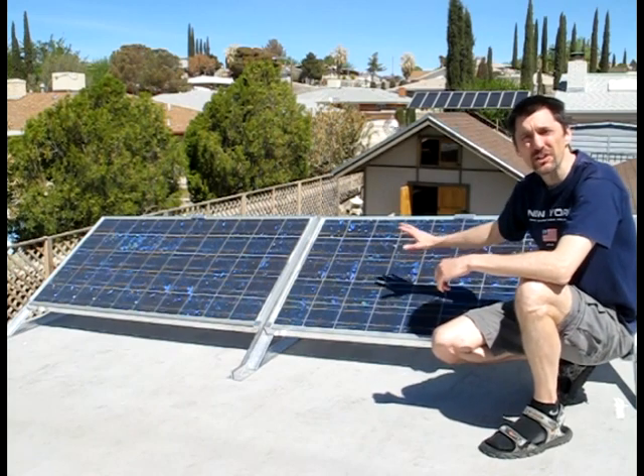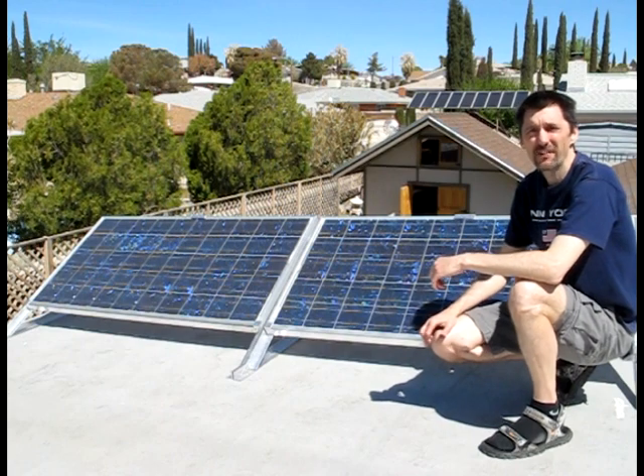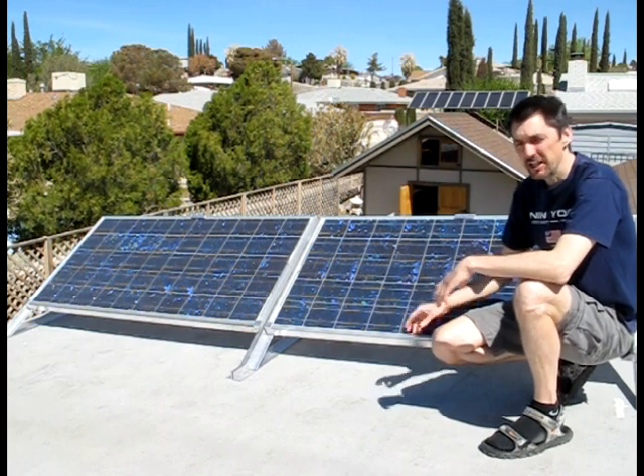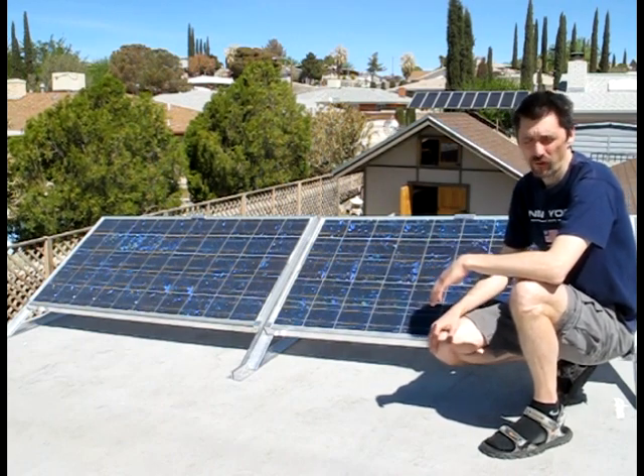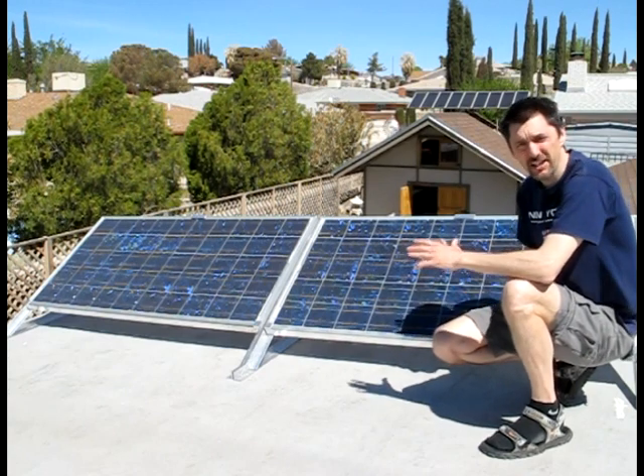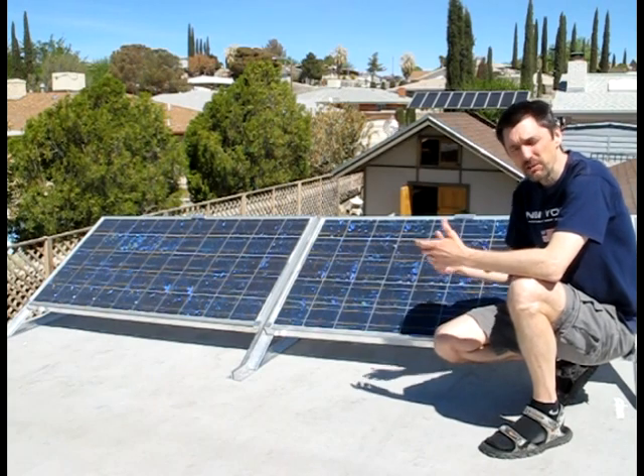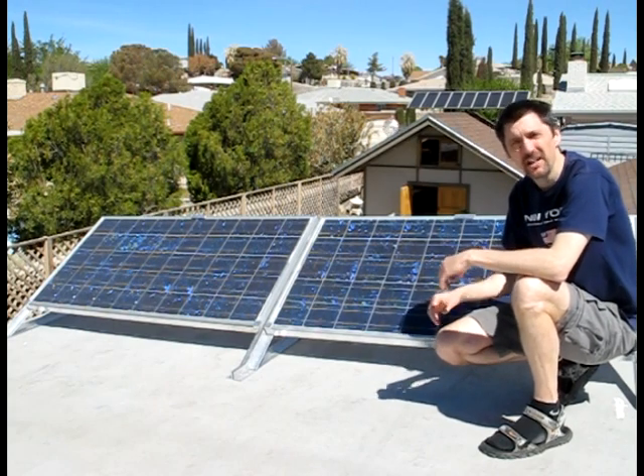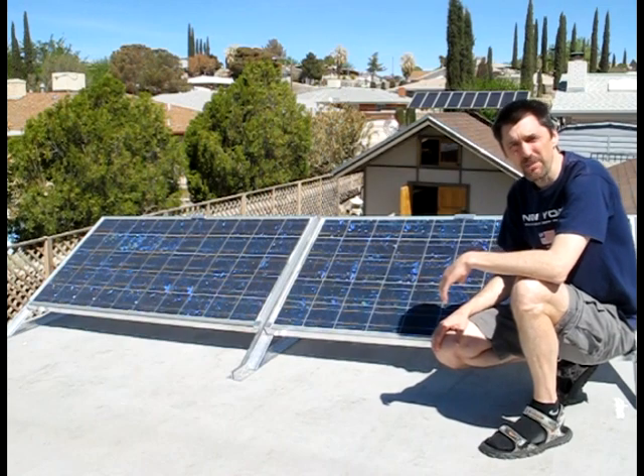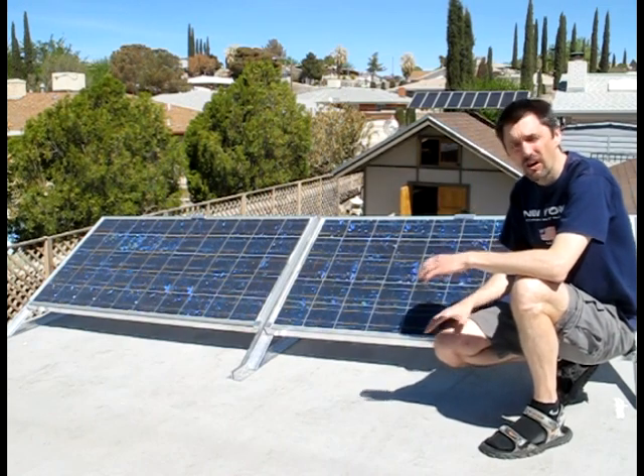It all starts here with these two Mitsubishi 165 watt, 6.85 amp solar panels. Each one is rated at 24.4 volts. We have them wired in series, meaning they're really acting as one panel at 48.8 volts. The reason we do that is it allows us to run a smaller wire, which is less expensive and easier to work with, all the way to our shed where all our equipment is.